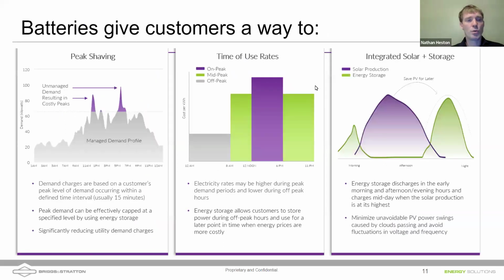Batteries give customers a way to back up their loads, back up their home. But there are also other things you can do with it, such as peak shaving. If you use some CTs to monitor the amount of power you're pulling from the grid, you can get that inverter to discharge those batteries to reduce the peaks you are causing when pulling from the grid. That removes some of the charges utilities impose once you go beyond a certain threshold in power consumption.